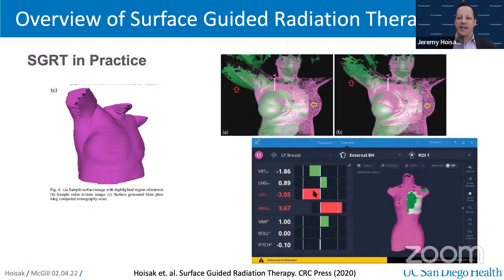And this will get displayed to the therapist as a calculation of offsets in 6 axes, so vertical, longitudinal, lateral, and then yaw, pitch, and roll, with a total overall magnitude displacement. And so they can apply manual adjustments to the patient, or they can move the treatment couch to bring the patient into alignment as these displacements are updated in real time, and then you can set thresholds as well, depending on the treatment site.